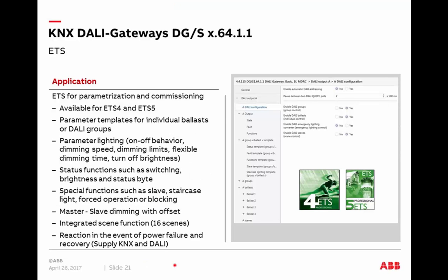Coming to the ETS: main features and parameters. ETS 4 and ETS 5 are supported. One nice feature is the ability to create parameter templates — a collection of parameter settings that can be used as a template for ballasts or groups. Instead of adjusting each ballast or group individually, you can apply the same parameters from a template for projects where most ballasts share the same settings. Of course, individual exceptions are also possible. Jürgen will show more about this in practice later.